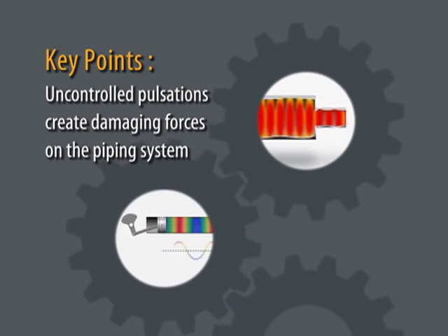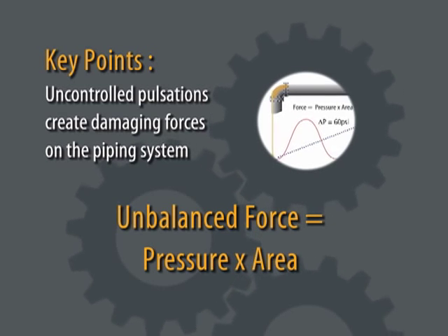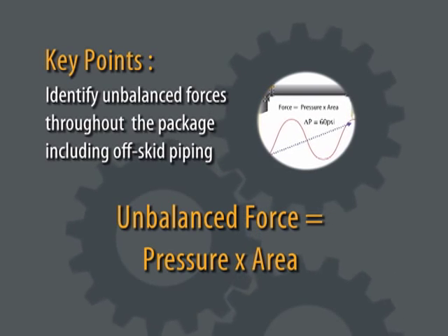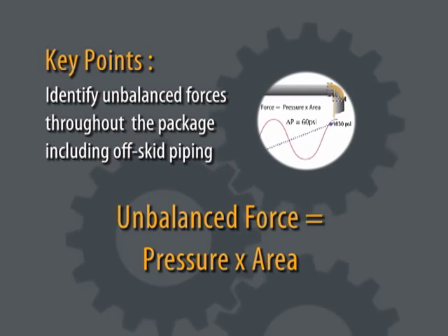Unless controlled, pulsations create damaging forces on the piping system. The unbalanced force equals pressure times area. Unbalanced forces must be identified throughout the package, including off-skid piping.